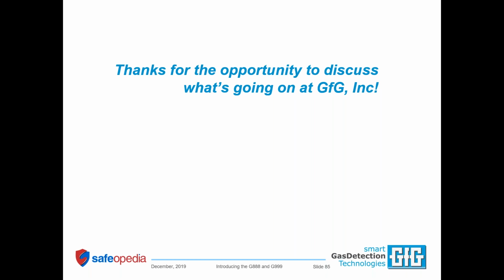The instrument is good to go for minus 30 Celsius temperatures, call that minus 22 Fahrenheit - use it all day long. Where you start to see things drop out is as you get colder than that. At minus 40 degrees, everything works, but for a limited period of time.